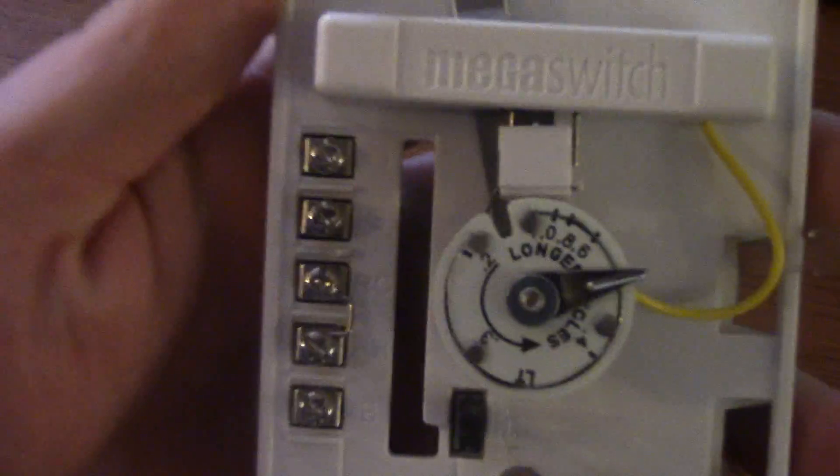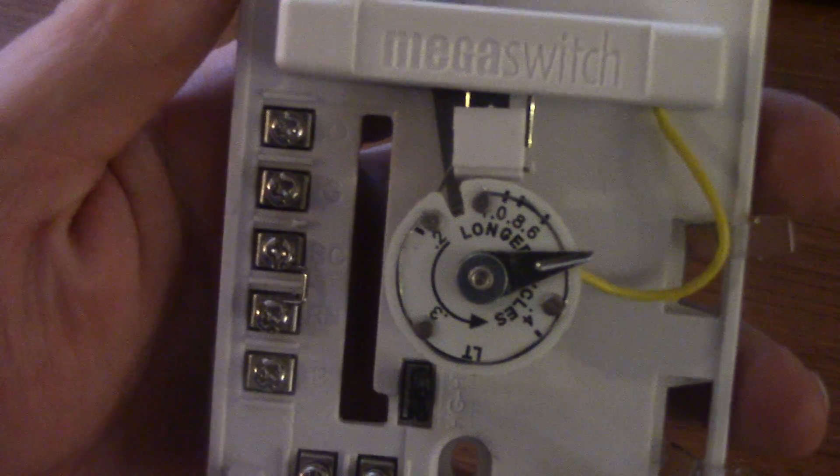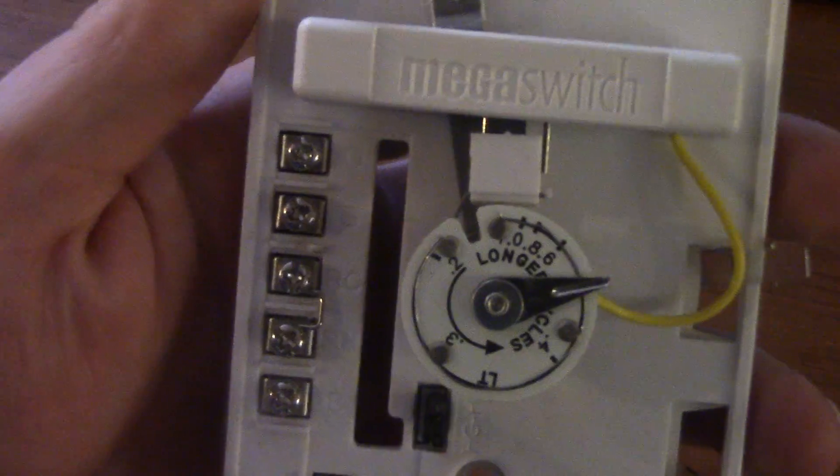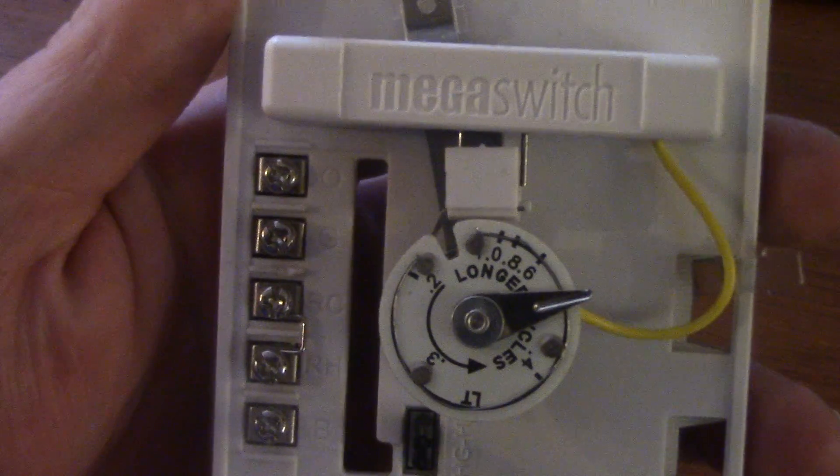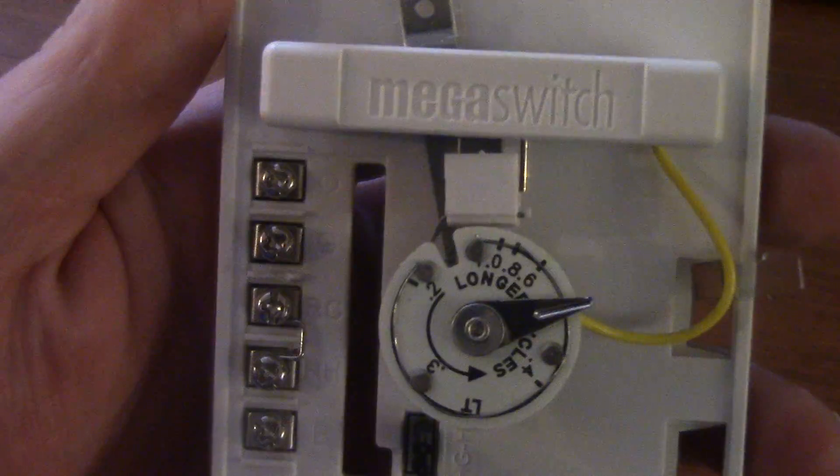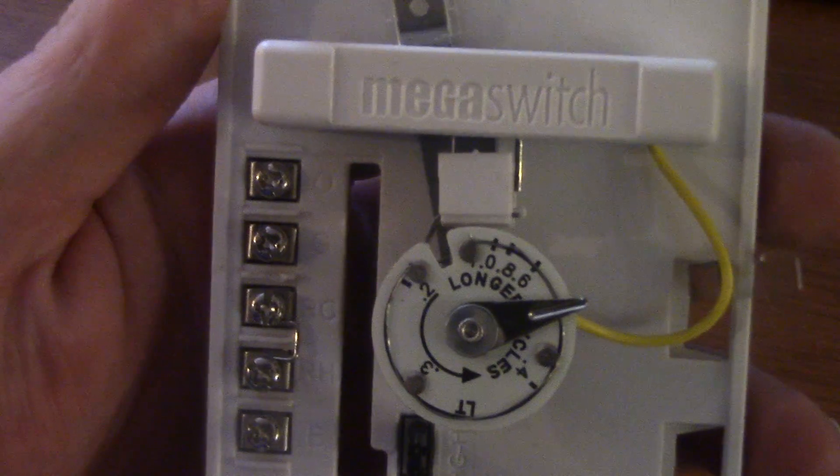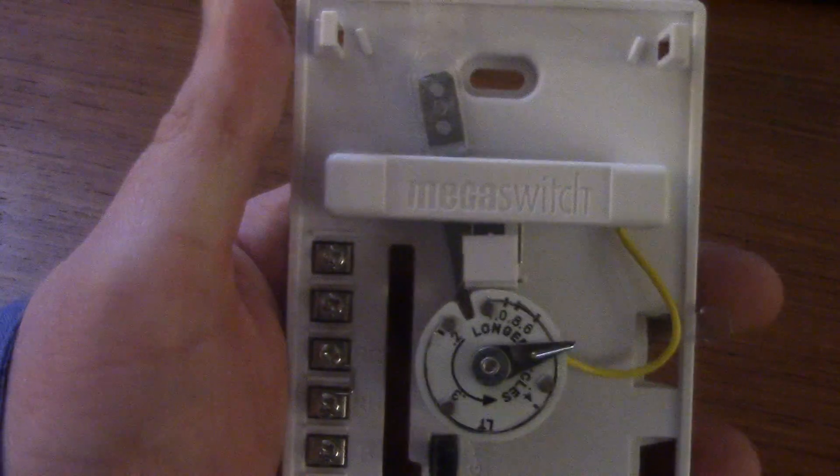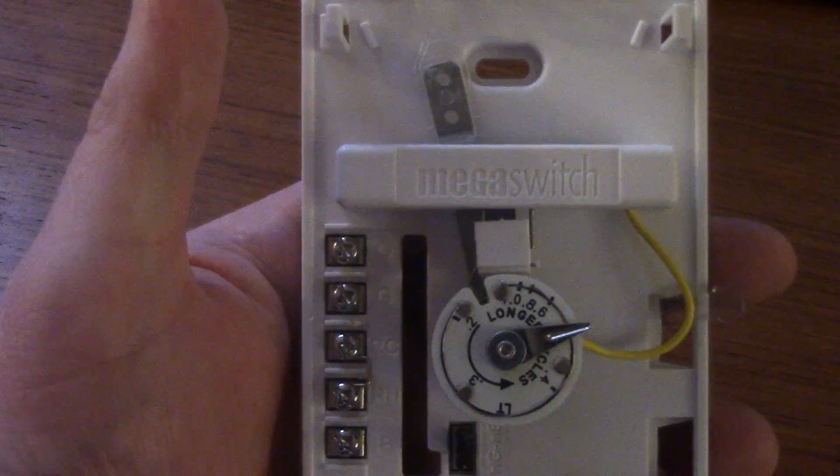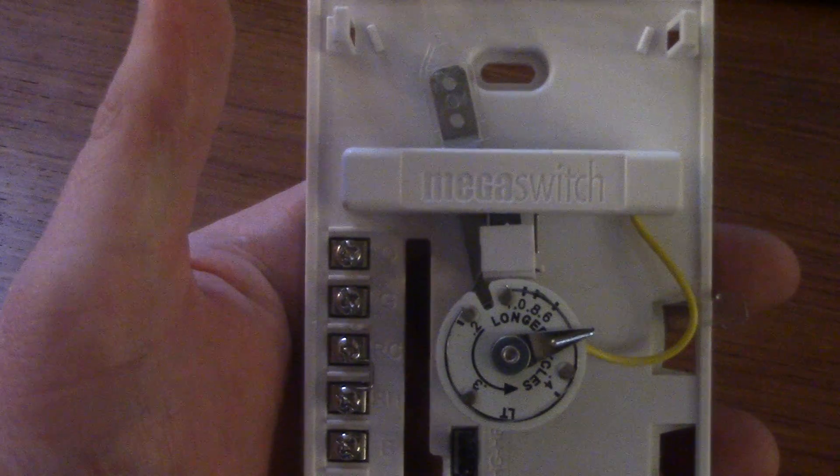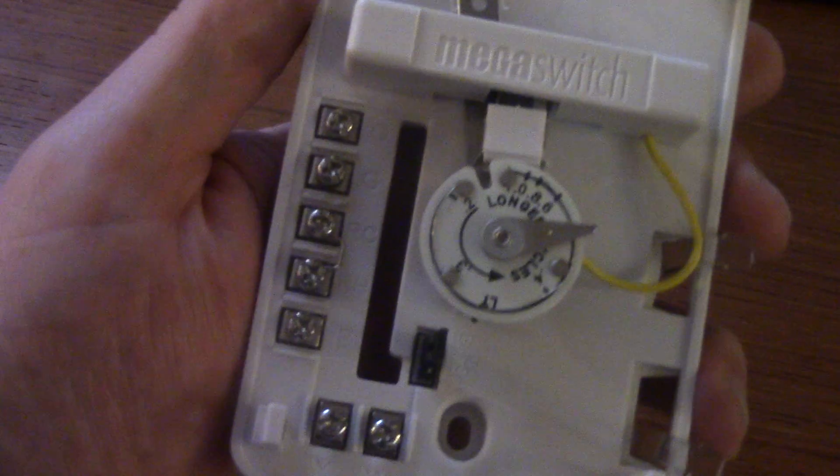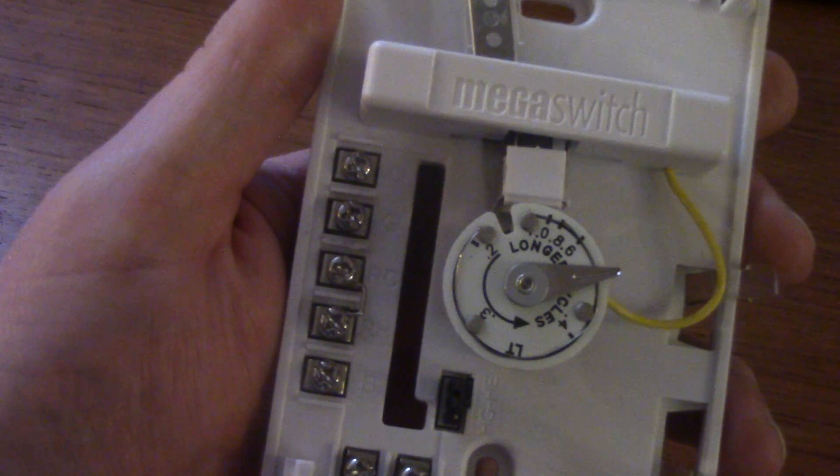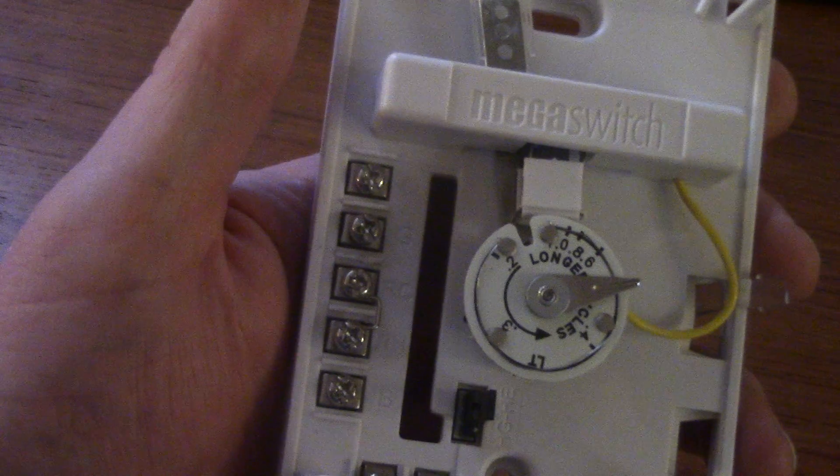The only reason we do the 10 wrap is you can do it 5 times or 6 times, but you have to admit it's a lot easier to divide by 10 than to try to divide by 6 or 5 or 8 or anything like that. If you tried to wrap the wire around twice, it will not give you the appropriate magnification for the amp draw. That's why we do the 10 wrap - just to make sure you get a good easy number to work with to divide by, and it picks up the signal real good.